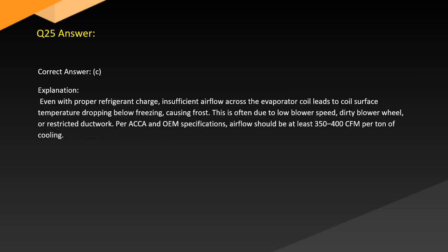Answer. Correct answer, C. Explanation. Even with proper refrigerant charge, insufficient airflow across the evaporator coil leads to coil surface temperature dropping below freezing, causing frost. This is often due to low blower speed, dirty blower wheel, or restricted ductwork. Per ACCA and OEM specifications, airflow should be at least 350-400 CFM per ton of cooling.